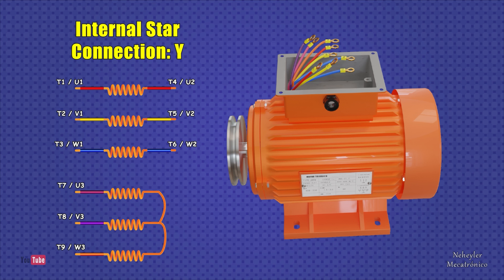A motor with an internal star connection means that the opposite terminals of T7, T8, and T9 are joined or connected internally in the motor. Therefore, the type of connection that must be made is specified on the nameplate, in this case, star.